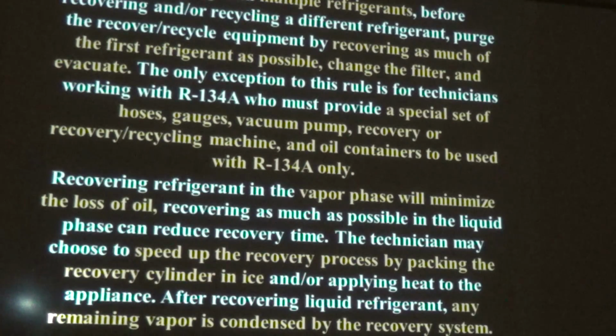Recovering as much as possible in the liquid phase makes it go faster. The tech can speed up the recovery process by packing the recovery cylinder in ice and/or applying heat to the appliance. After recovering liquid refrigerant, the last step always is to recover as a vapor in order to get all of the refrigerant out. Always recover. The last step of recovery is to recover as a vapor.